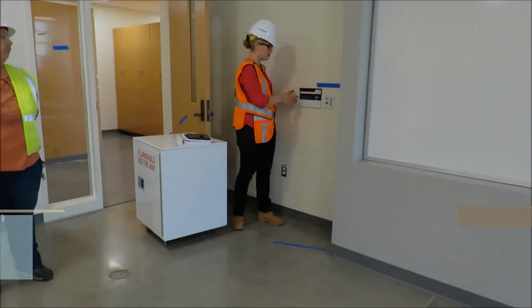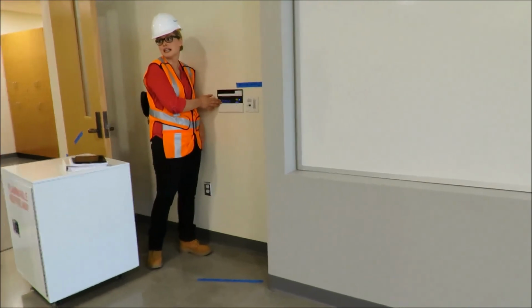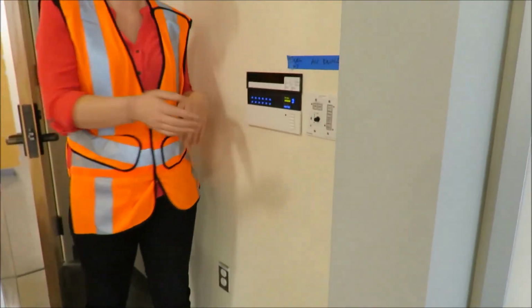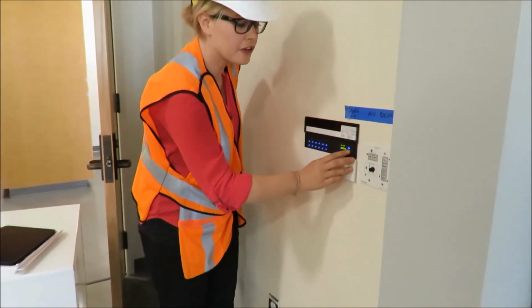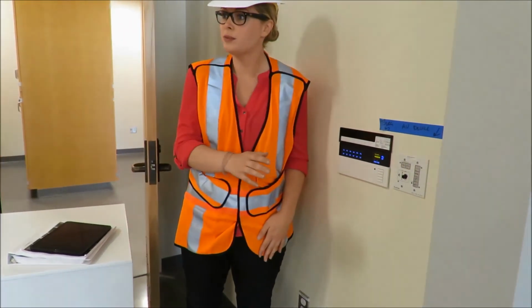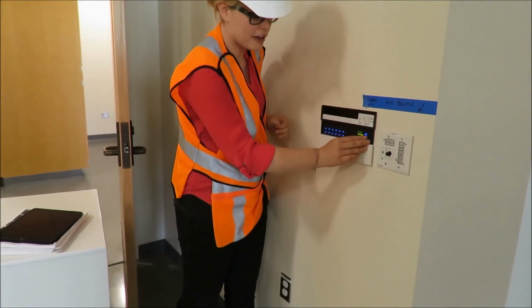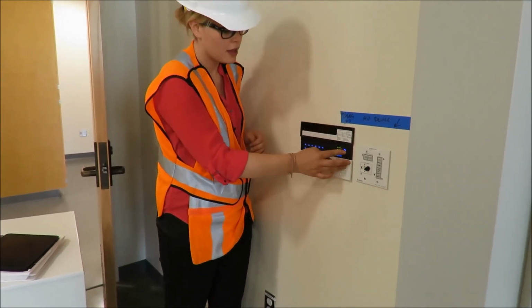This means that when you're out of program mode, if somebody plays with these, it doesn't save that as a preset scene. They can change the levels temporarily, but if you go back and push scene 1, it goes back to 100%. There are other options. There's save always, which automatically saves it if somebody plays with it. There is save by OK, where they can change it and then hit OK, and it changes the scene.